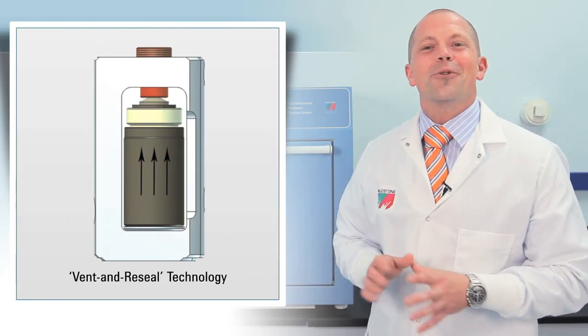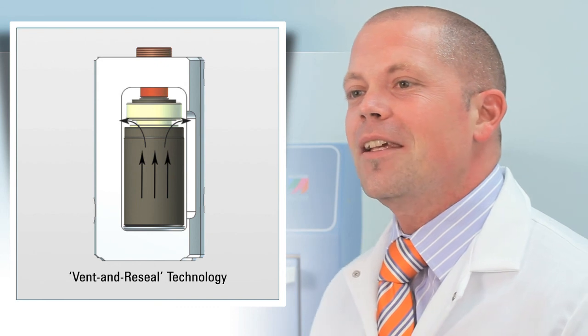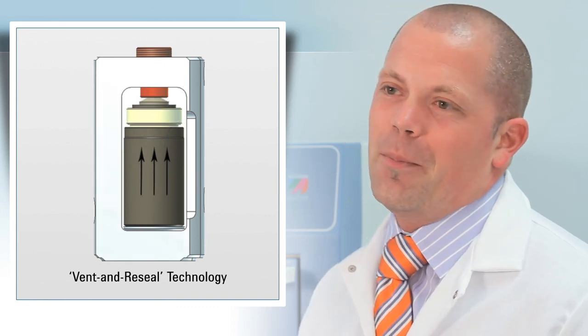Milestone uniquely offers true vent and reseal technology which eliminates excessive venting, giving more complete digestions and better data quality.